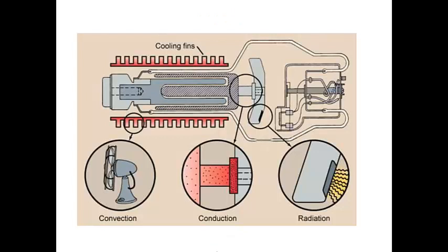Basically, the heat produced is lost or dissipated by radiation, conduction, and also convection. Most of the heat produced in the X-ray tube is lost by radiation during the exposure, where the anode may glow and emit infrared radiation. However, some heat is also conducted through the neck of the anode to the rotor and glass envelope. This will also increase the temperature of the oil bath, and this will convect the heat to the tube housing and to the room air.